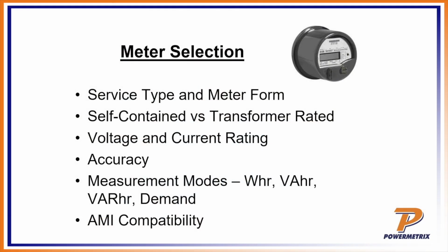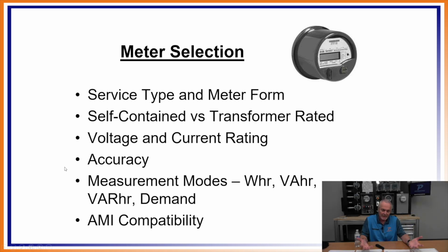So meter selection. First you have to decide on the service type and the meter form, right? We've talked about this previously. We basically fall into two groups on the meters, self-contained and transformer rated. And we know that the self-contained has no external CTs or PTs, right? It's got some internal CTs, but the transformer rated has external CTs. So with that, we can go to a lot larger size CTs, as you're going to see here in a minute, which affects the amount of current that they can handle.